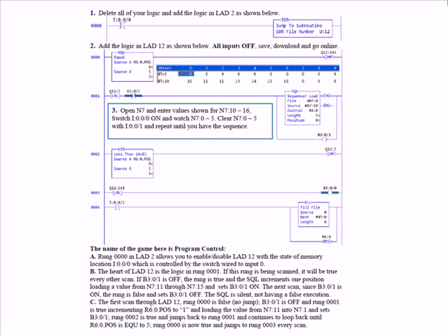If we go to the next rung, rung 2, and we look, it says less than 5. If the position, R60 position, is less than 5, then we jump to 7. Okay, and 7 is jumping backwards. We're jumping from rung 2 back to rung 1. And of course, after we've executed the SQL once, we're going to be equal to 1. So it will be less than 5. We'll jump backwards to 7.